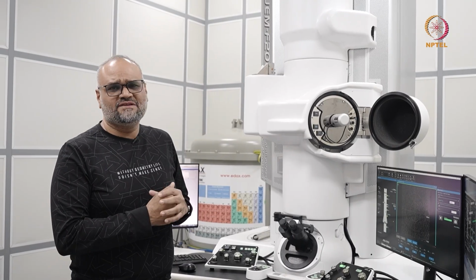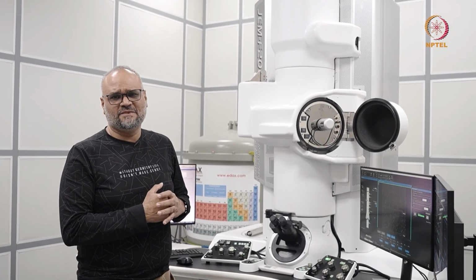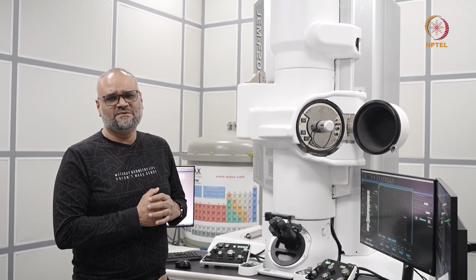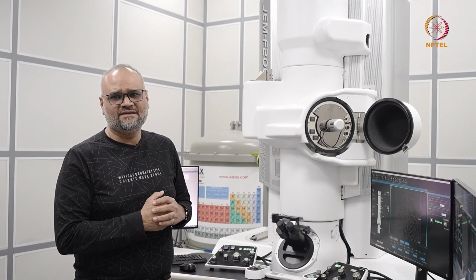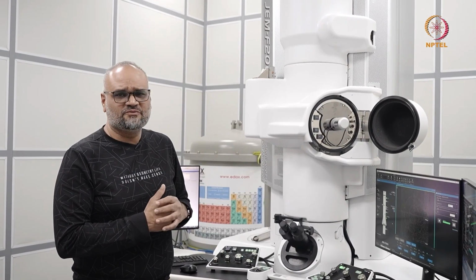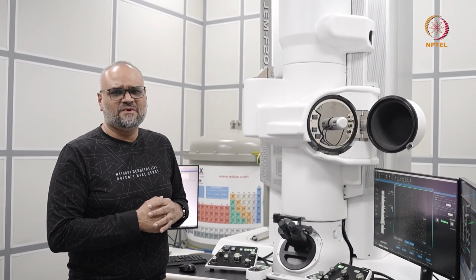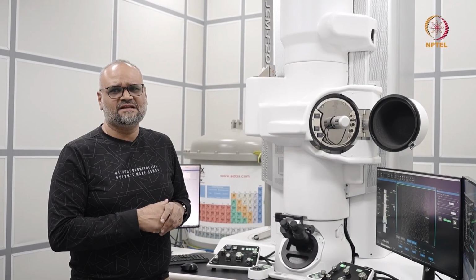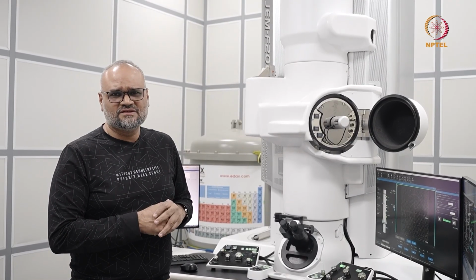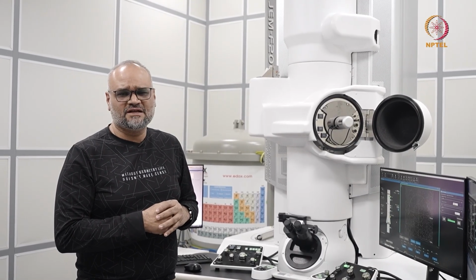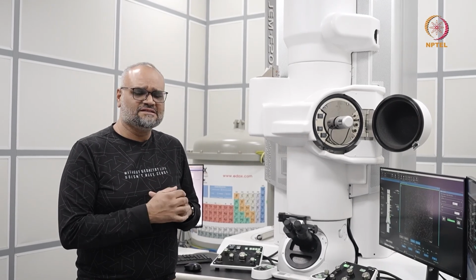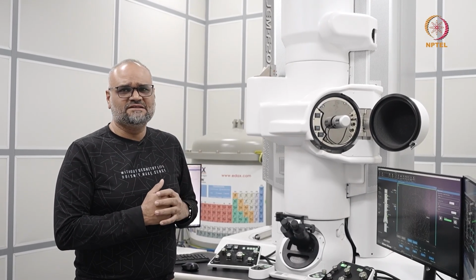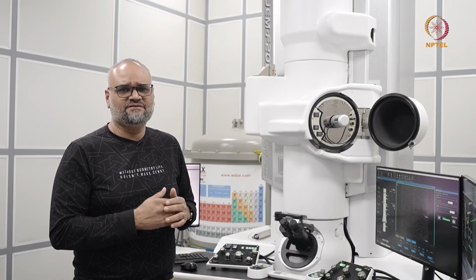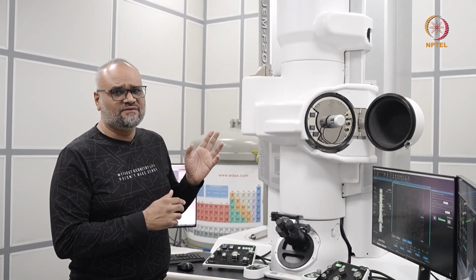So here we have the JEOL JEM F200 microscope. It's a cold field emission gun TEM operated at 200 kV. This instrument is also equipped with an EDS detector. If you remember, in the previous lectures, you've seen an example of the 2100 TEM, which has a lanthanum hexaboride filament. If you remember your lessons on the types of emitters, you have thermionic emitters, you have Schottky FEGs, and then you have a cold field emitter.